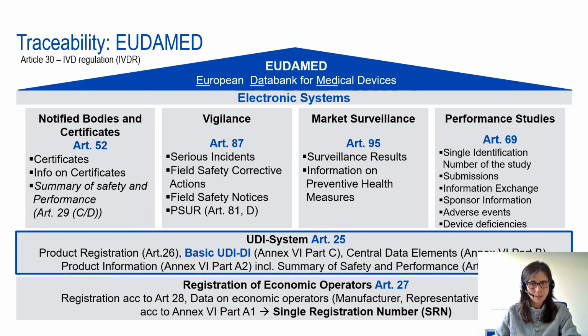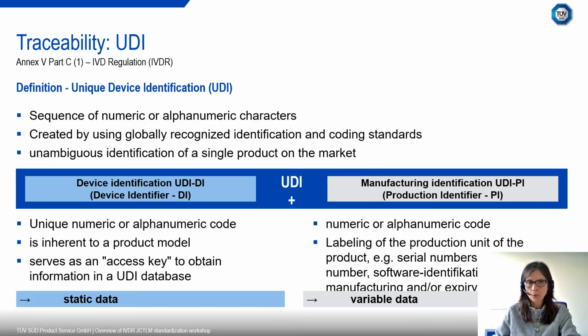The regulation also enhances the traceability of the overall system. The regulation introduces a single registration number that identifies manufacturer, authorized rep, and importer. And for the traceability of the device, it implements a unique device identification system. That is a sequence of numerical or alphanumeric characters that are created by recognized identification standards, and that will allow for an exact identification of the device on the market. There is a part that's specific to the device, called the UDI-DI, and the variable data that identifies, for example, the lot number of the device.